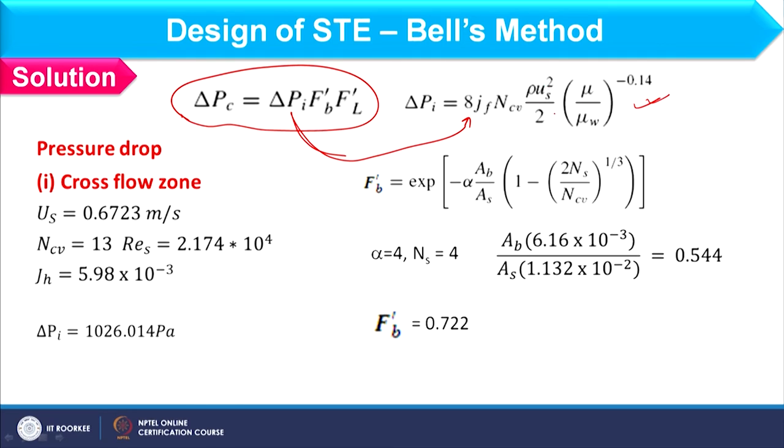So here US you already know, NCV 13, and the Reynolds number you can obtain like this, and then you can find out the JH value as shown over here. So depending upon this you can find out the delta PI value as 1026.014 Pascal, right. And after that you can find out FB dash as well as FL dash. So for FB dash, you should consider the alpha value, otherwise all parameters will remain the same.